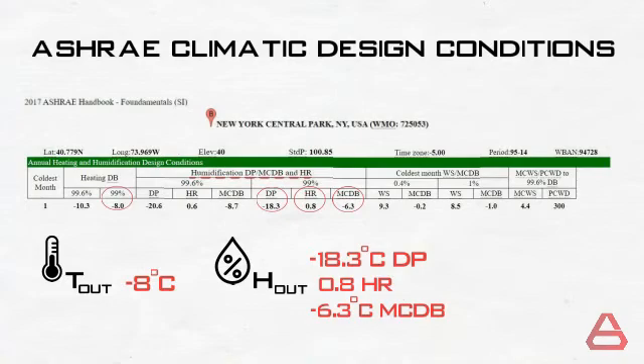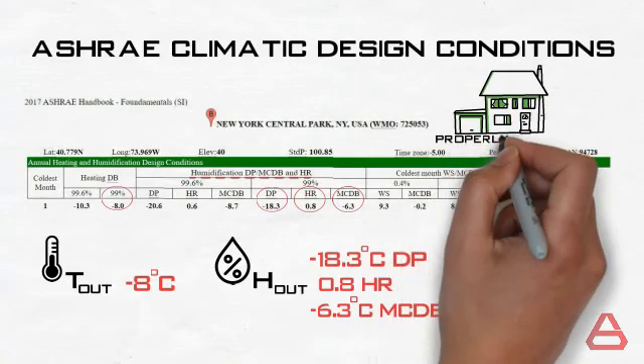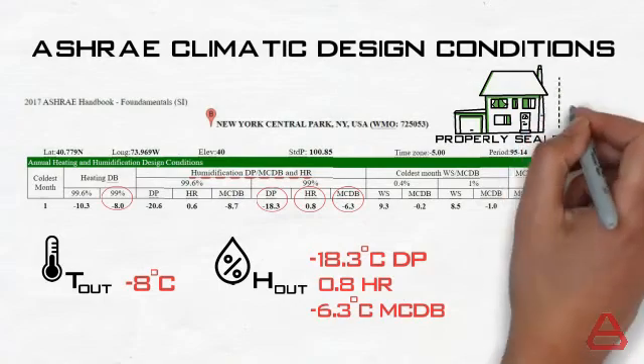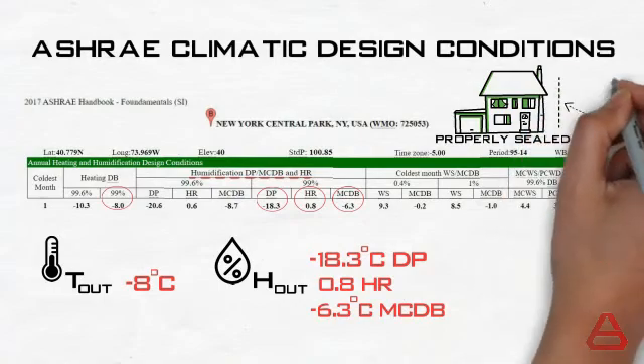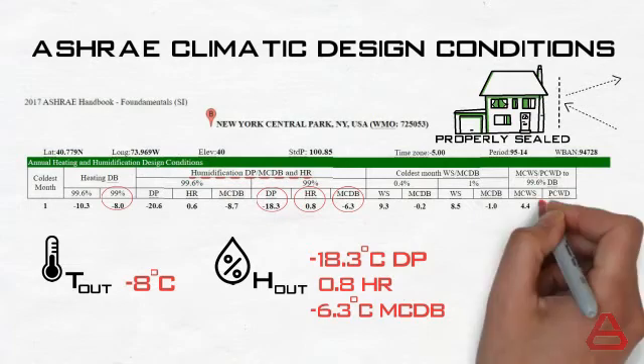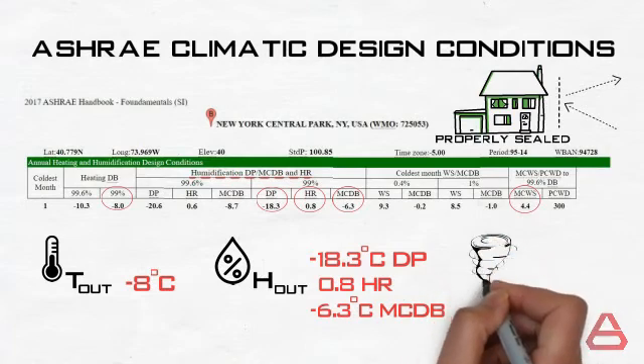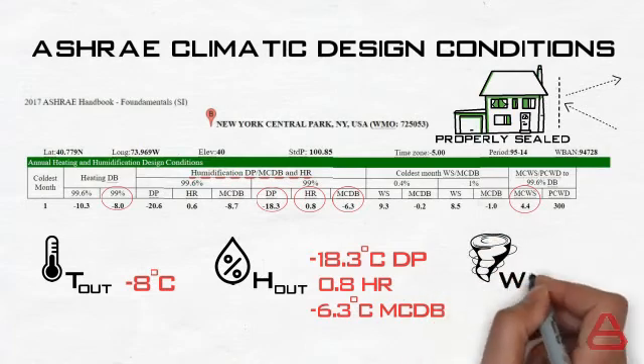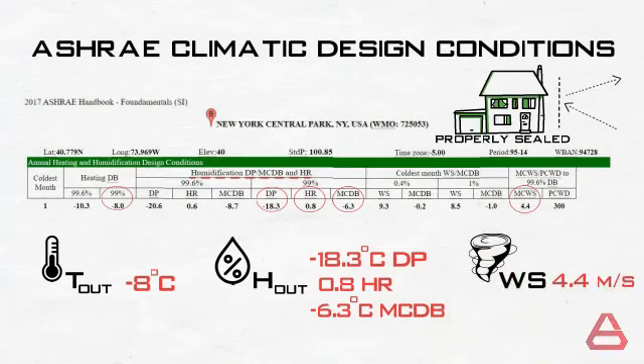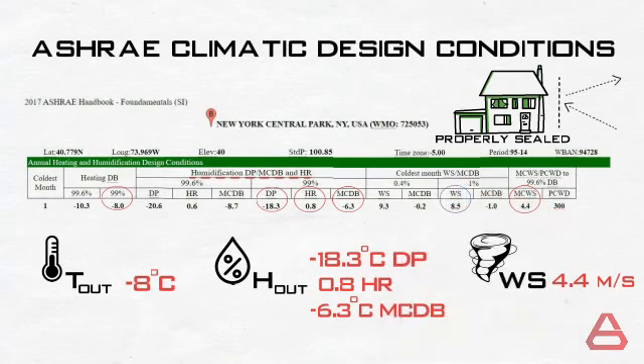For wind speed, we will assume Sarah's apartment to be a properly sealed apartment, thus avoiding having the highest load from the infiltration as previously discussed, and therefore we will choose the mean coincident wind speed at the 99.6 percent dry bulb temperature, which is 4.4 meters per second. Remember, for maximum infiltration loads in poorly sealed houses, use the other value shown as 8.5 meters per second.